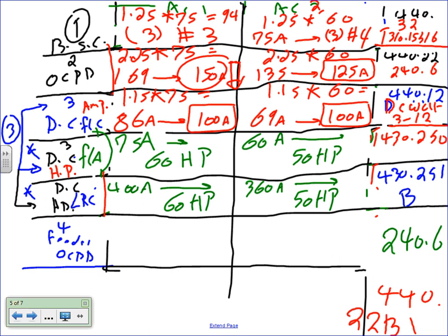Any questions, guys? Okay, so besides the disconnect, number 4 is the feeder overcurrent protection device. The feeder overcurrent protection is a piece of cake. Just one question. Yeah, go ahead. I'm looking at table 430.251b. Did you just round the value? If there's no 400, you go to the next, 450, or whatever. Oh, okay. You go up. Yep, that's how we get the horsepower rating for the equipment.